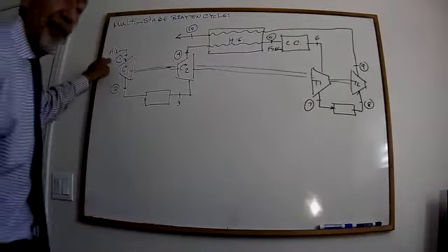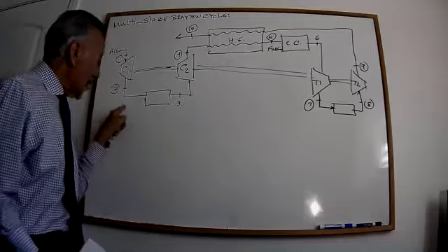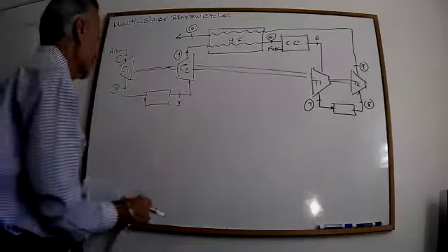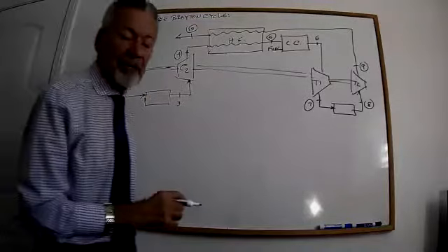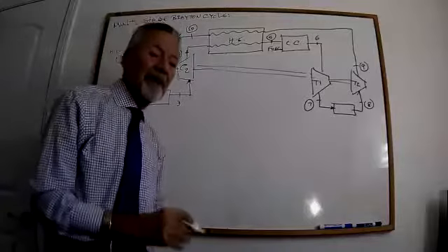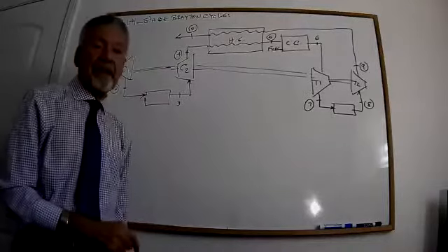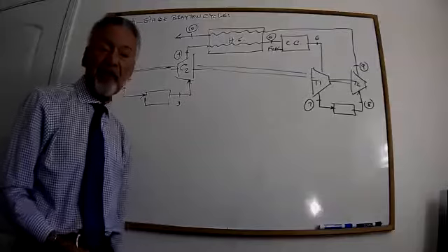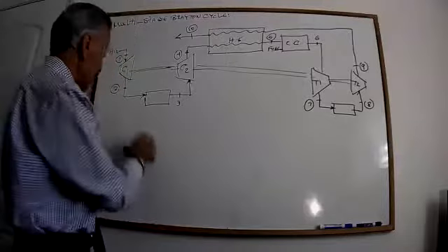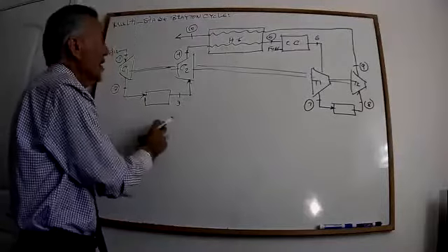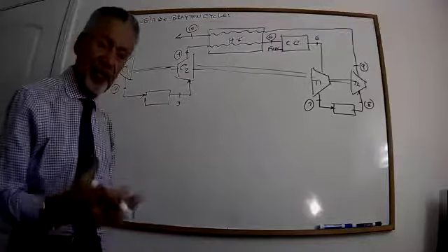Air at ambient temperature and pressure enters the compressor and comes out at point 2. Now, when I'm looking at it, I want to take it to the second compressor. But I have a problem. The pressure doesn't bother the compressor, but the temperature does, because at point 2 I have a high temperature. If I take it there, guess what happens? It will destroy the compressor. So I have to bring this temperature down in order to take it to the second compressor. Therefore, I use a heat exchanger device.